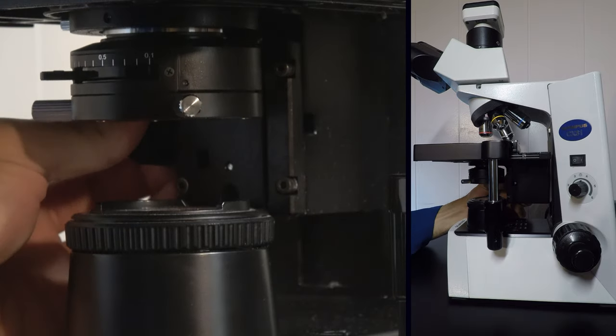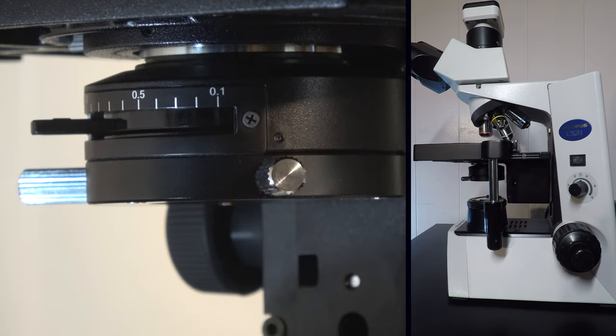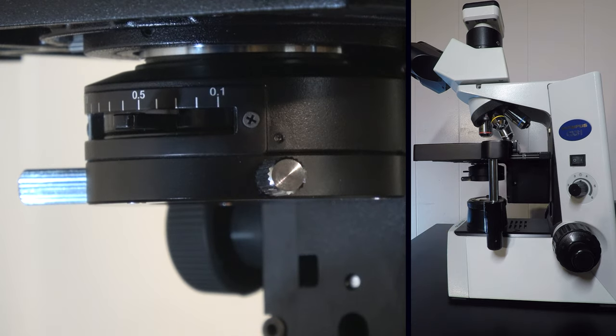The condenser is just below the stage. Move it to the upper position and then down about a half a centimeter. The iris diaphragm is located on the condenser. Move this lever to the halfway position.